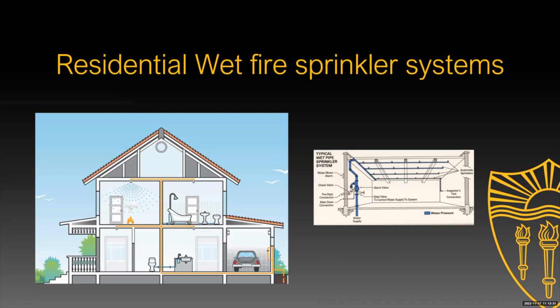The other wet charge fire sprinkler system to mention is the residential fire system. These are similar to the industrial one in that they take water straight from the supply side and feed it to all the sprinkler heads in the residence. The key thing is there are differences in design in how the residential system is made up, and because of that, there are different backflow requirements. We'll talk more about that as we go along.